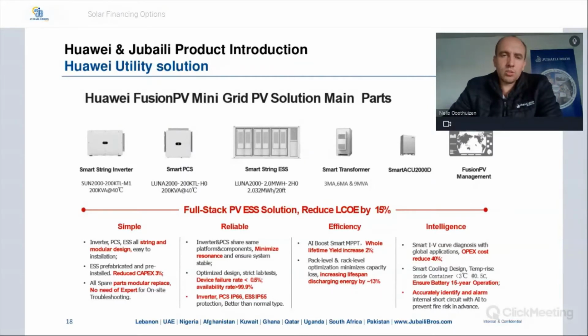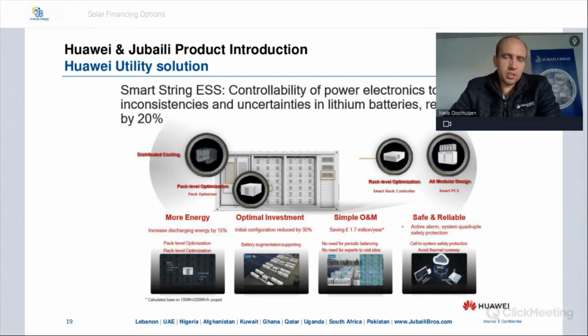Then the smart transformer station. This is what is required for you to step up or step down the voltage to whatever your requirement or your connection point is on the grid. It's typically available in a 3 MVA, 6 MVA, and 9 MVA configuration, with output voltages differing from 11 kilovolts up to 33 kilovolts. Then the SmartACU2000D, that's the communication device for your utility solution. And then Huawei has got its own Fusion PV management system, or your own monitoring system. So that gives you the full solution available from Huawei on a utility project.